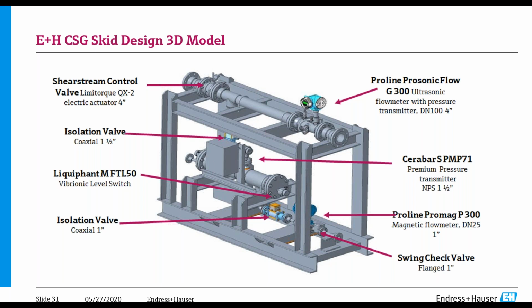So that means that the transducer face is not sitting in the direct flow path of the methane gas and solids carryover coming through the flow meter. And this is a key factor, because if you've got a leading edge inside the flow path, even if you have titanium sensors, it's very much prone to abrasion. And that's the key point measurement, or primary measurement, on the flow meter, and if you have failure on the transducer, then you lose the measurement point. So we wanted to make sure that we manage that well.